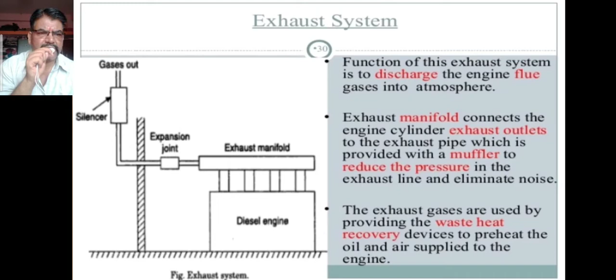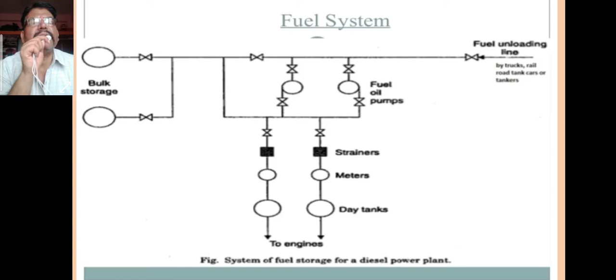Now the fuel system. The fuel unloading line is connected to the fuel oil pump and the bulk storage. The fuel oil pump is connected to the engine with the help of strainers, meters, and the tanks. In the fuel system, the main flow is arranged with piping and equipment such as heaters, bypasses, shut-offs, drain lines, relief valves, strainers, filters, flow meters, and temperature indicators. The flow plan depends on the type of fuel, engine equipment, and the size of the plant.